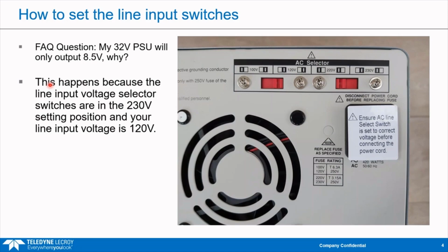This particular slide and the one afterwards actually came about because of frequently asked questions. I've had this question quite a few times: my 32 volt power supply will only output 8.5 volts, why? This happens because of the line input selector switches being set to 230 volts instead of 120. We ship them that way because we're never sure whether they're going to be delivered to the US or to Europe, so for safety, we set them to 230.